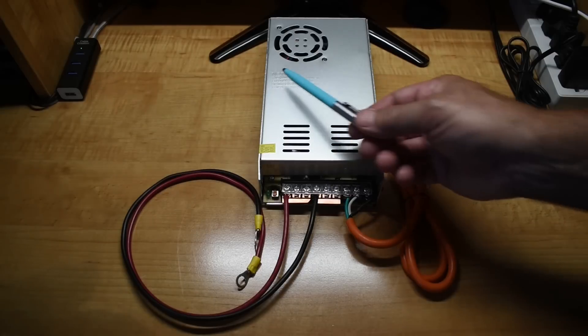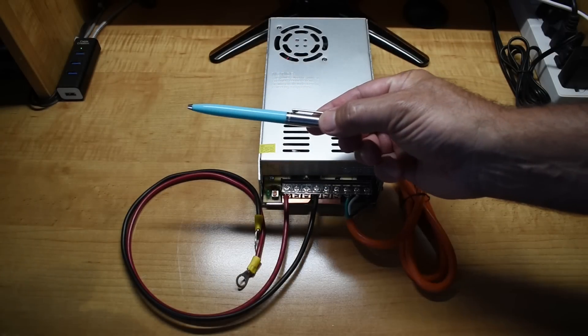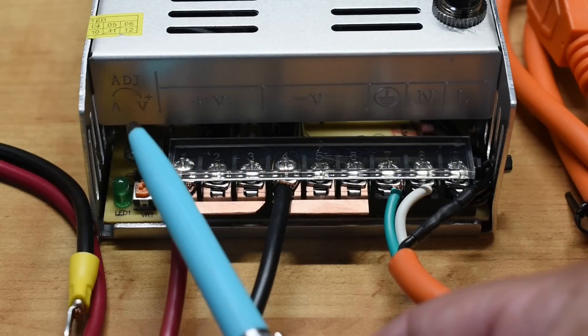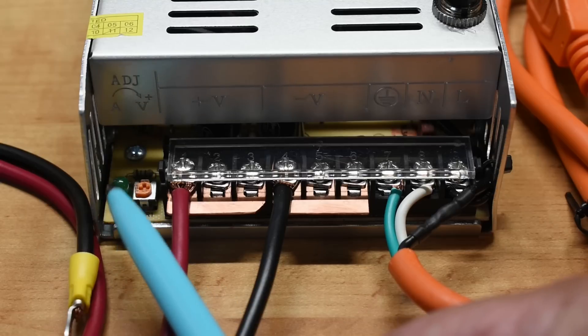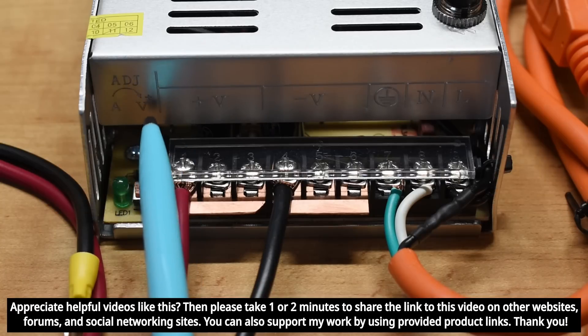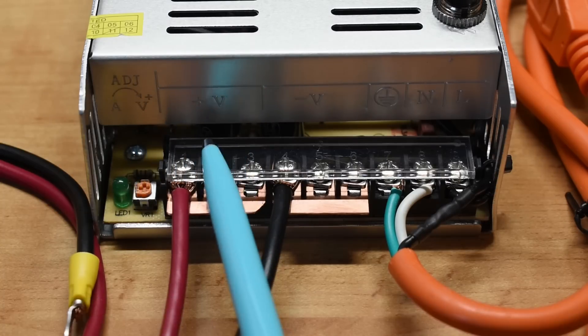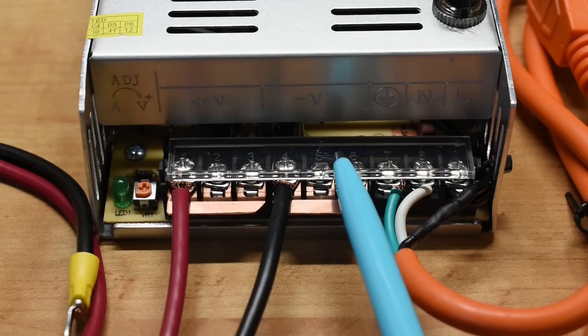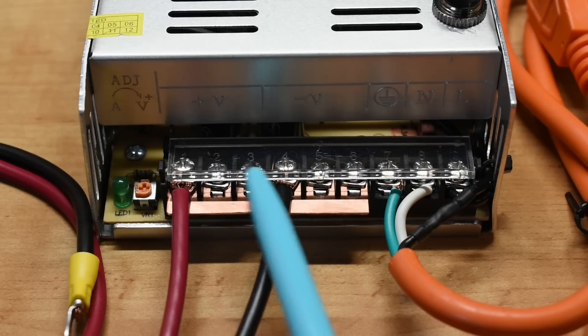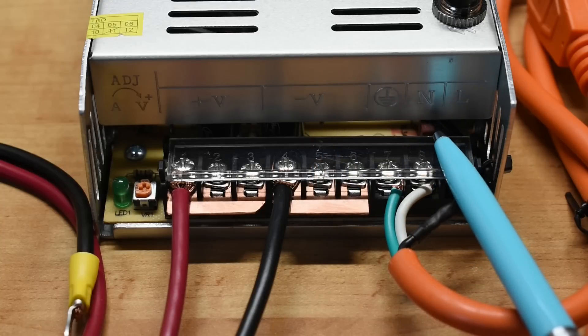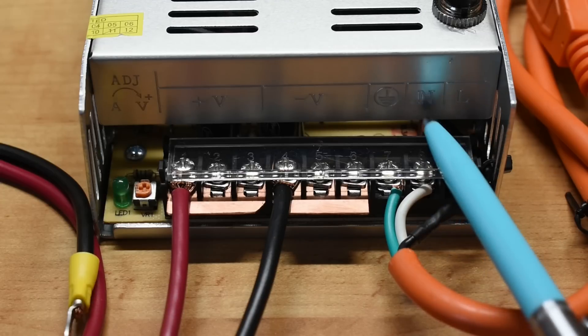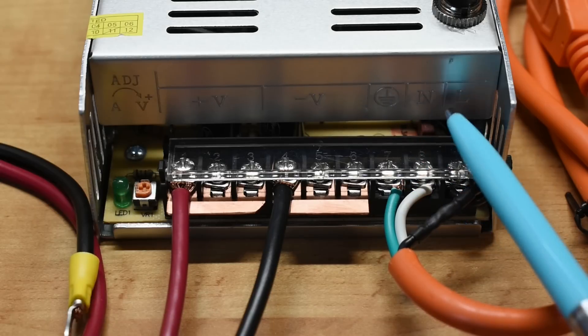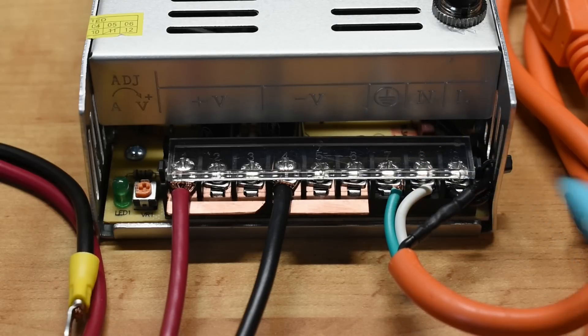On this side of the unit here is the model number and you can see that right over here. A closer look at the terminal strip, you can see on the back wall there's markings. So you have the power indicator light right here, and you can see right here is the potentiometer. It says clockwise to increase voltage. Over here it says voltage positive output, over here is your voltage negative output. So all three screws right here is the positive, all three screws here is your negative. And over here it says AC input. You can see it says N for neutral, that's right here. Here's the symbol for ground, that's the green wire. And over here it says L for line, and that's my black wire.